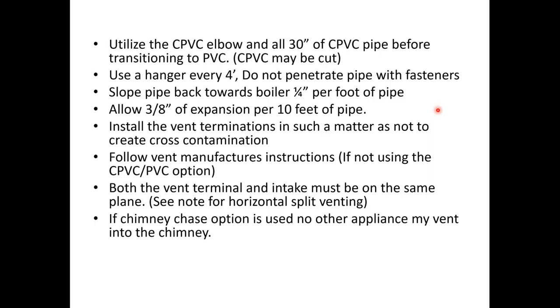That boiler is designed to take care of all of the condensate. We want to allow that to happen. Let it deal with it. Let it pump it elsewhere. If we slope it towards the outside, we usually wind up with ice dams and nuisance lockouts on the products. We don't need to insulate the vents. We don't want to do that. And if we're using the chimney chase options, nothing else can go into that chimney.